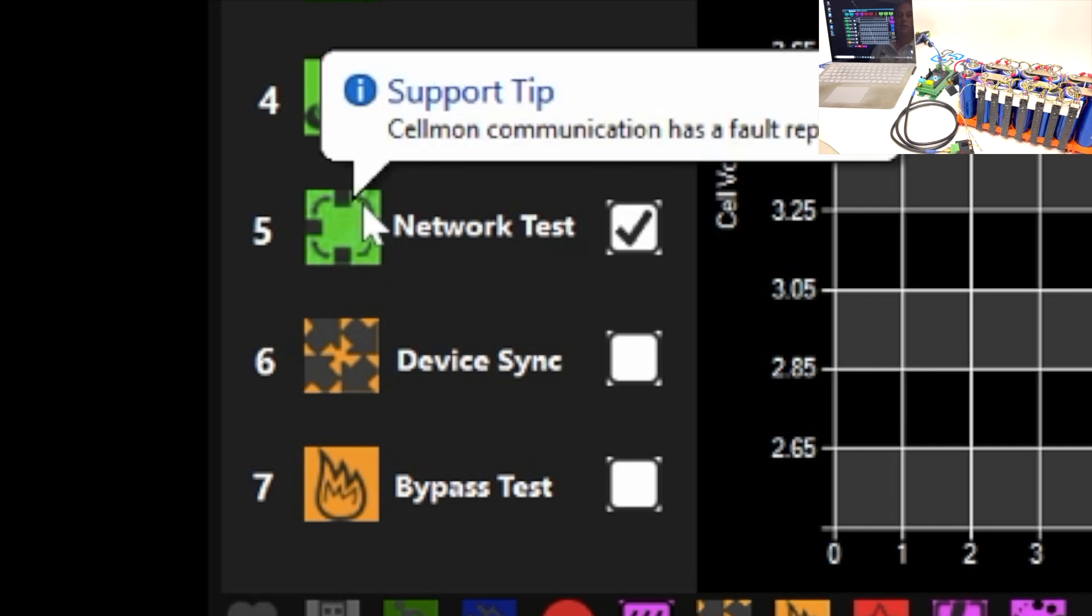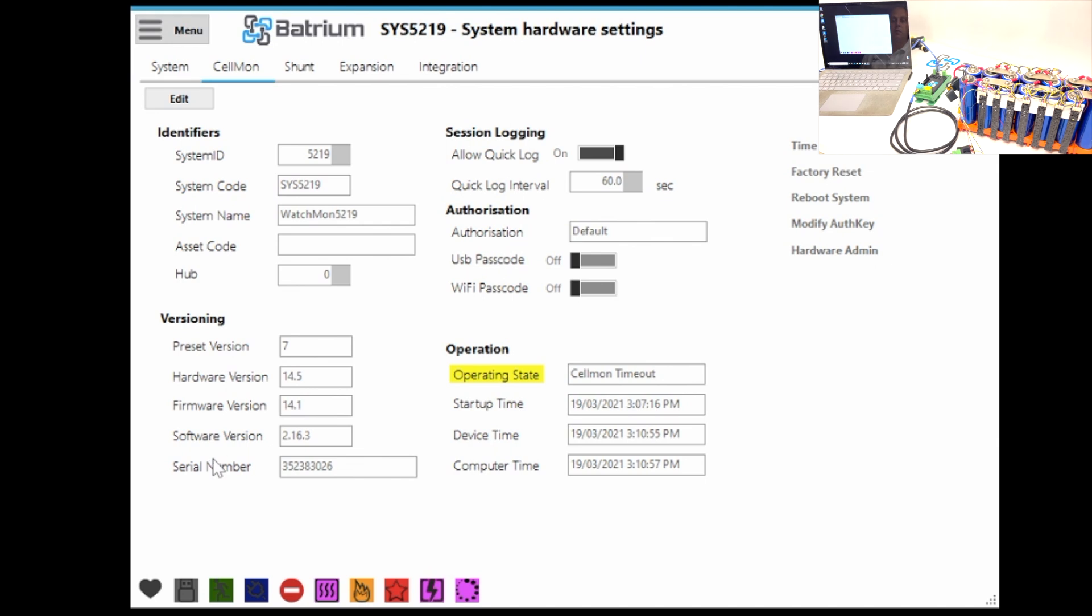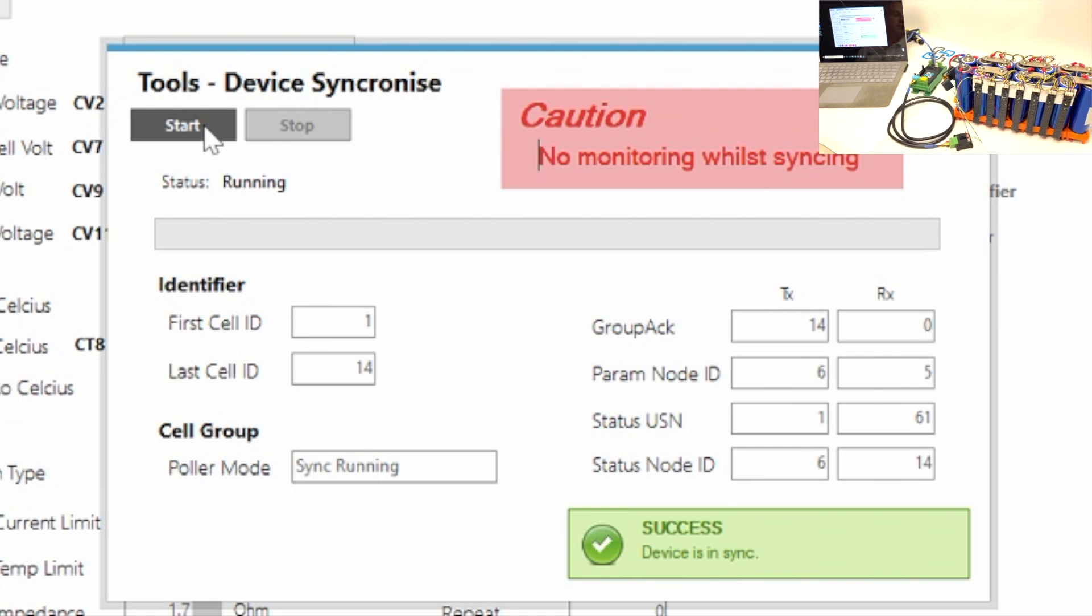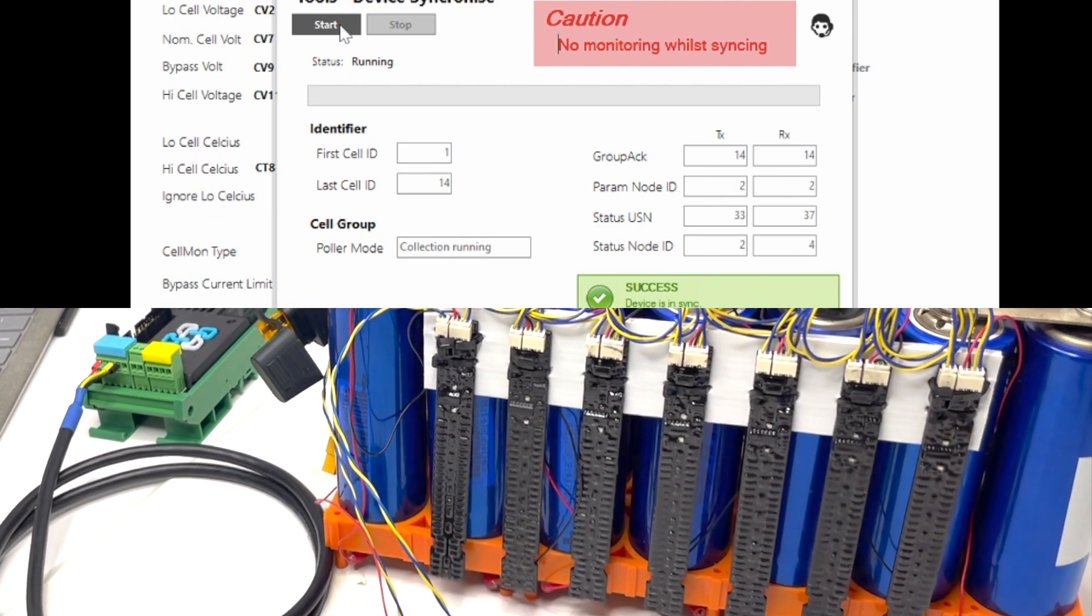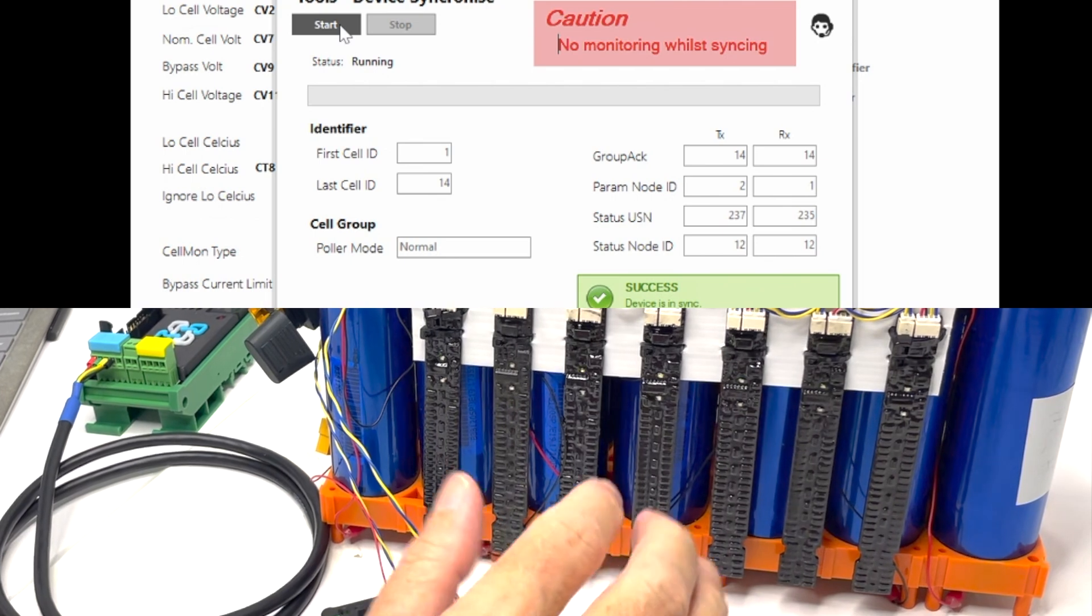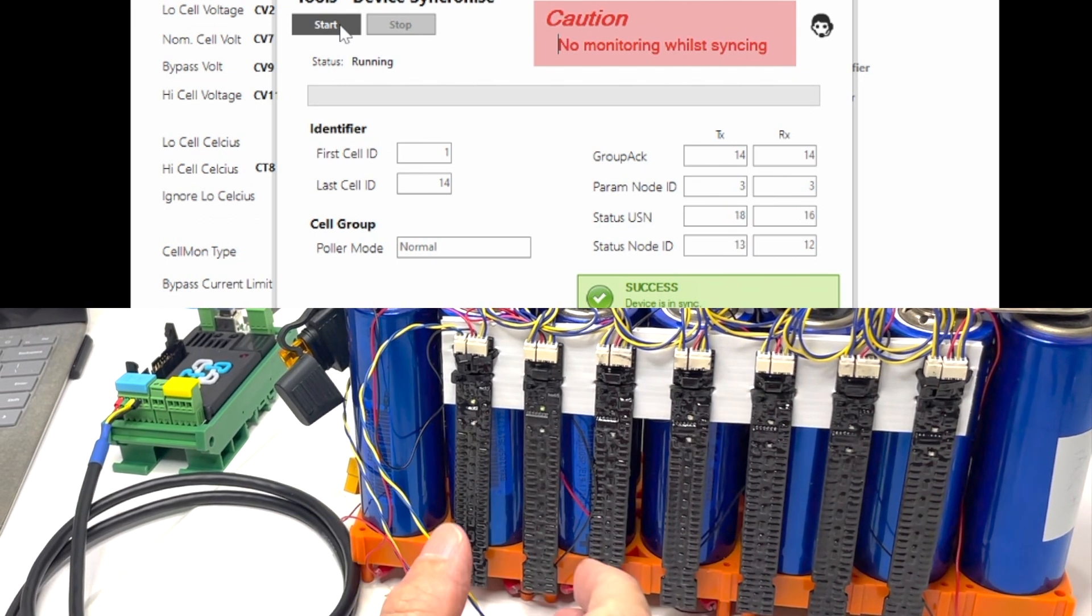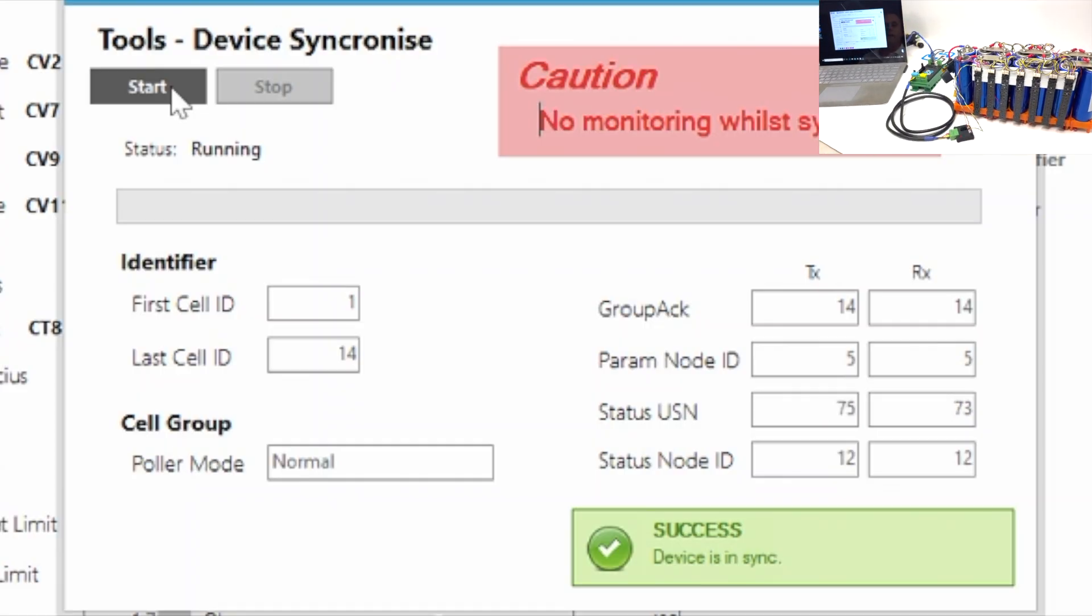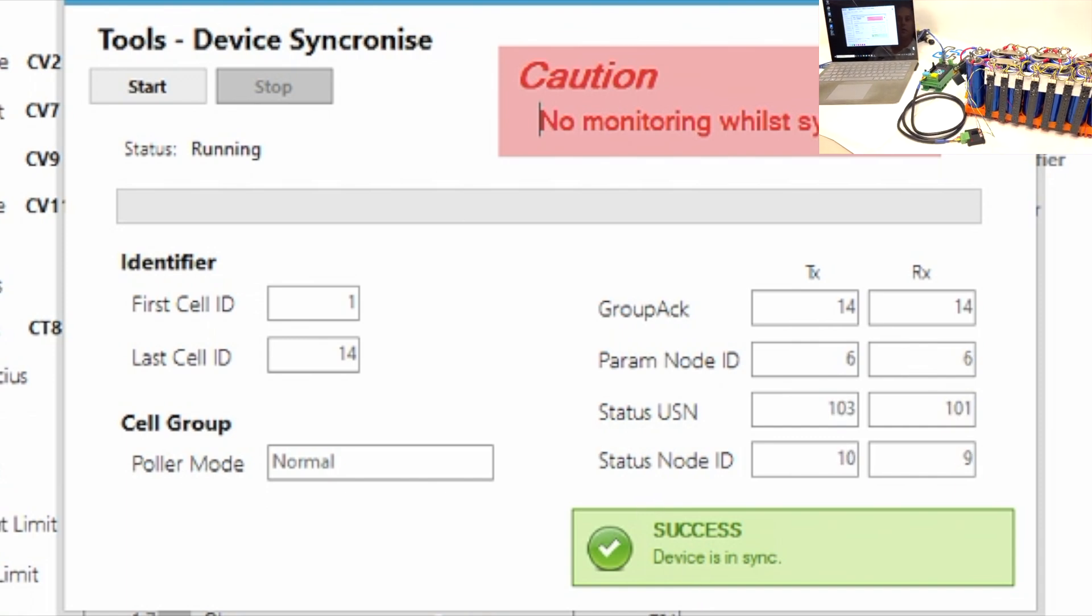The device sync hasn't occurred so let's now do that. So we go down to device sync and we press it. We come in here and we press start and it's just as simple as that. This will now go away and configure each of the devices. On the devices here we can see that they're going through a flashing sequence and it's reconfiguring each one and making sure the first one is assigned to one, the second one is assigned to two, third is assigned to three and working its way through. And you saw there with the flashing sequence that it goes through a set of steps of identifying and assigning each one, making sure they're in sequence, making sure it's heard from them and then setting the configured parameters that are defaulted when we ran the wizard. Now that we can see on screen it says device is in sync, we know that this step is complete. So we can go close.